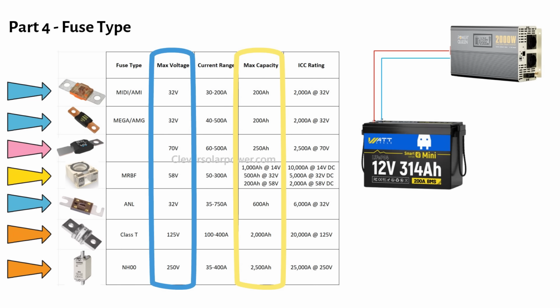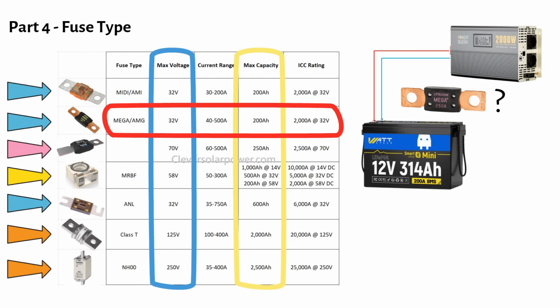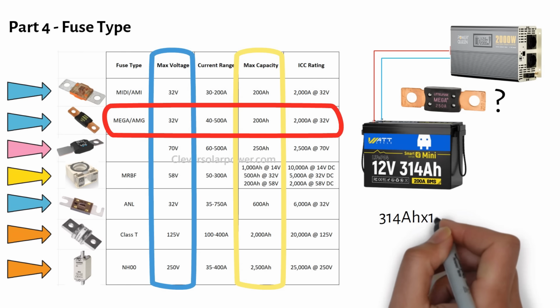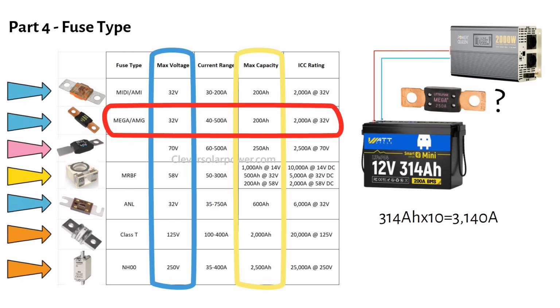So in our first example of the 12 volt 2000 watt inverter, we needed a 250 amp fuse, and the battery was 12 volts at 314 amp hours. So can we use a mega fuse? At first, you would think so, because the mega fuse is rated for 32 volts max. But the short circuit current interrupt rating is only 2000 amps at 32 volts. And as a rule of thumb, the possible short circuit is 10 times the battery capacity. So 314 amp hours times 10 equals 3140 amps. So a mega fuse is not suited. The fuse we should use is an MRBF, ANL, Class T or NH00 fuse, because these can interrupt the short circuit current while the mega fuse cannot.